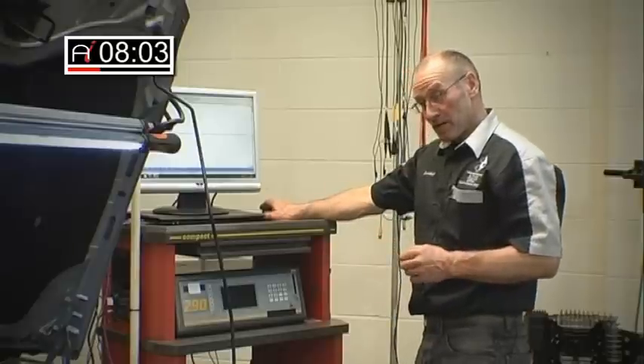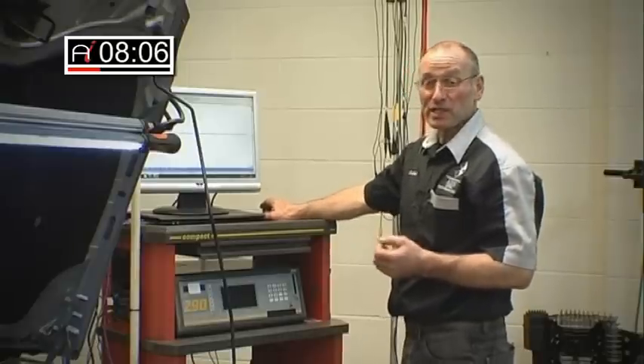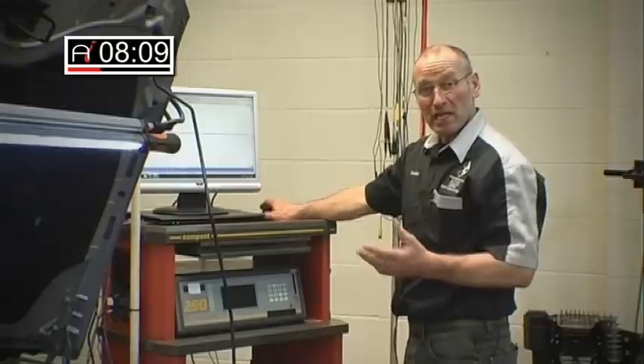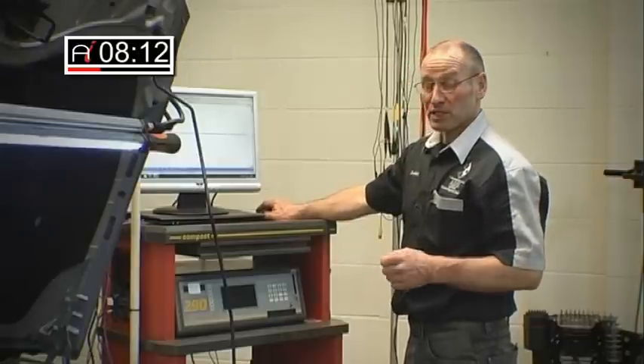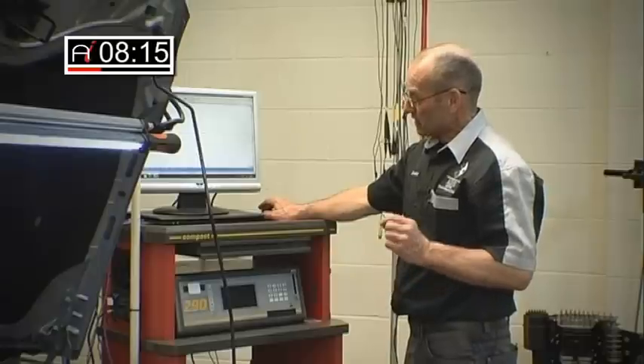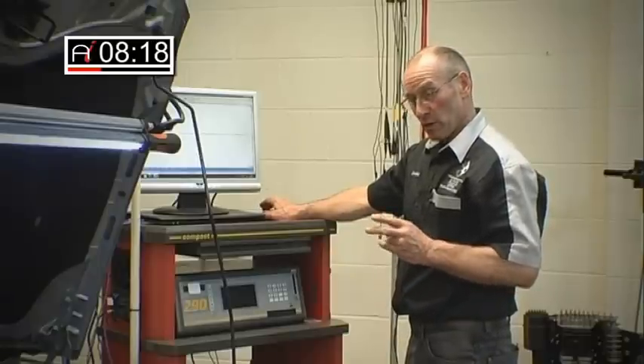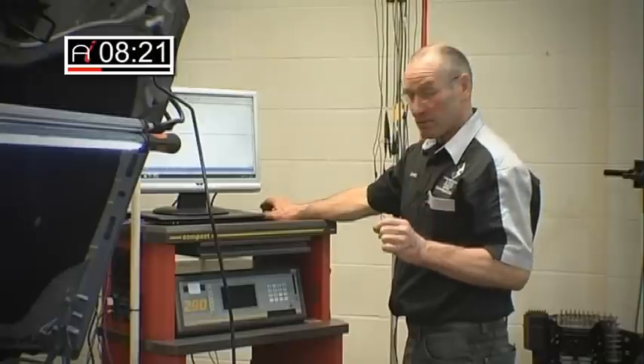a new feature, frequency. If I then select frequency, I can now select the range, which has now been converted to a frequency reference, and if I open that box up, you can see there's an automatic function, a 0 to 2 kilohertz, 0 to 2000 hertz, and 0 to 20,000 hertz. This particular device operates approximately from 1000 hertz at idle to about 9600. So let's say it's 0 to 10,000. So it's going to be appropriate to set the 0 to 20 range. So the second channel, which we've set up, will now convert that digital signal to an analog representation.